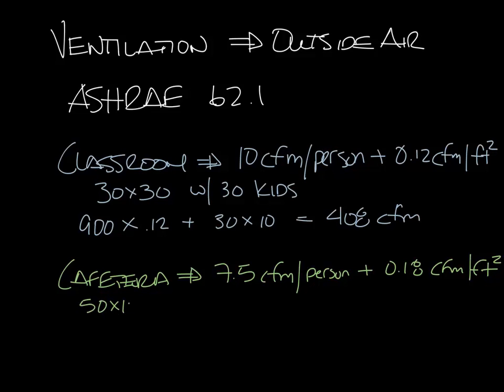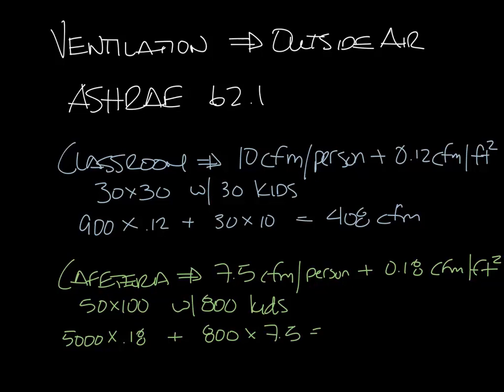And for the cafeteria, let's say it's 50 by 100 with 800 kids in it. So that would be 50 times 100 is 5,000 square feet times 0.18 plus 800 kids times 7.5, and that comes up to 6,900 CFM of fresh air.